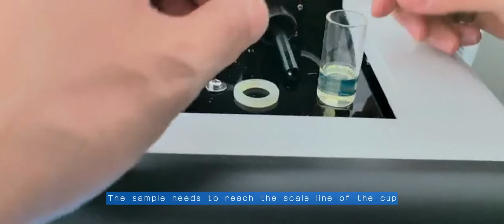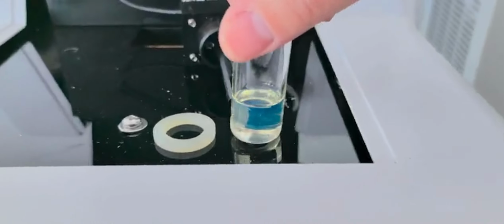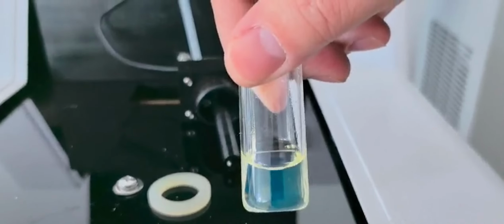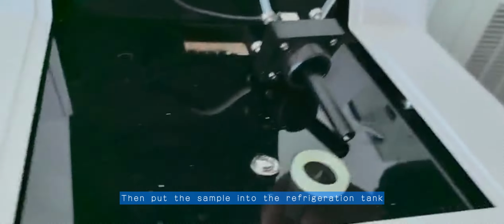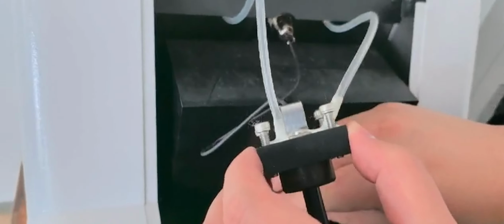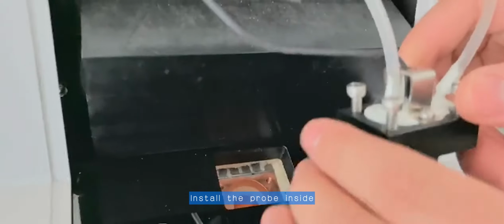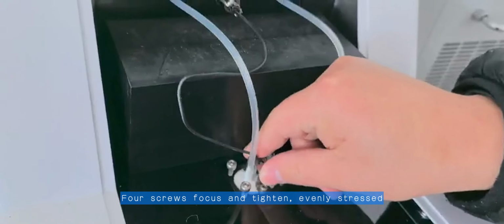The sample needs to reach the scale line of the cup. Then put the sample into the refrigeration tank. Put the gasket back in place. Install the probe inside. Focus on the 4 screws and tighten them, evenly stressed.